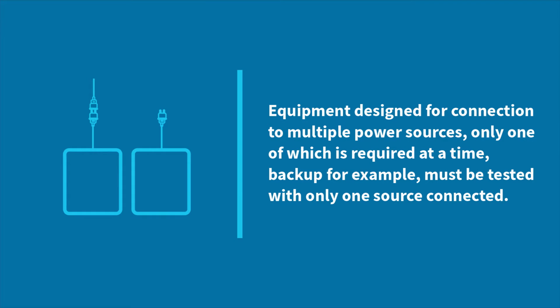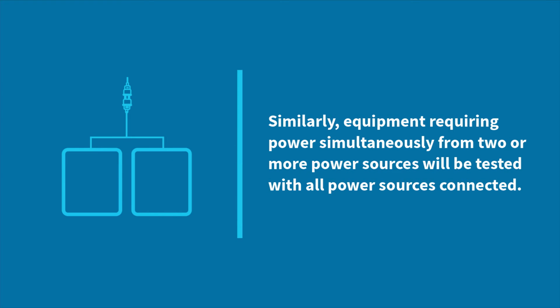Equipment designed for connection to multiple power sources, only one of which is required at a time, backup for example, must be tested with only one source connected. Similarly, equipment requiring power simultaneously from two or more sources will be tested with all power sources connected.